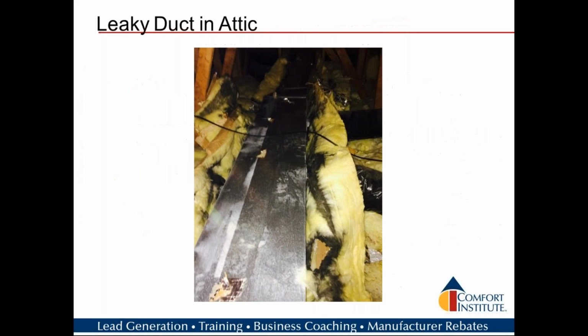So yeah, we sure can. I mean, here's one that a tech had, in fact, just sent me a picture of last week, where he's in an attic, he pulled back insulation, and he saw all the dirt on the underside of his insulation. He's up there looking. I mean, he's out there going for leads. He pulled back the insulation to see if it's leaking. He's got a real good picture of it, and he's able to take that down to the homeowner and show them they've got a real big problem. To fix this right here, duct sealing is going to be required.